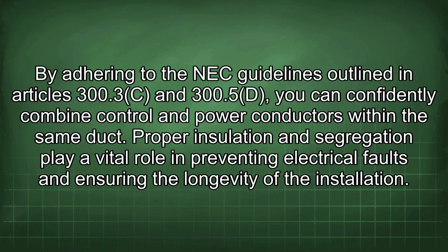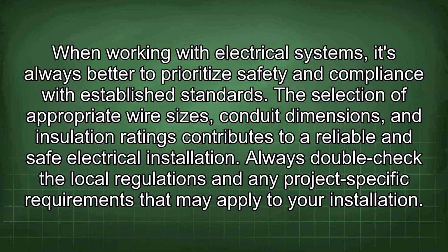within the same duct. Proper insulation and segregation play a vital role in preventing electrical faults and ensuring the longevity of the installation. When working with electrical systems, it's always better to prioritize safety and compliance with established standards. The selection of appropriate wire sizes, conduit dimensions, and insulation ratings contributes to a reliable and safe electrical installation. Always double-check the local regulations and any project-specific requirements that may apply to your installation.